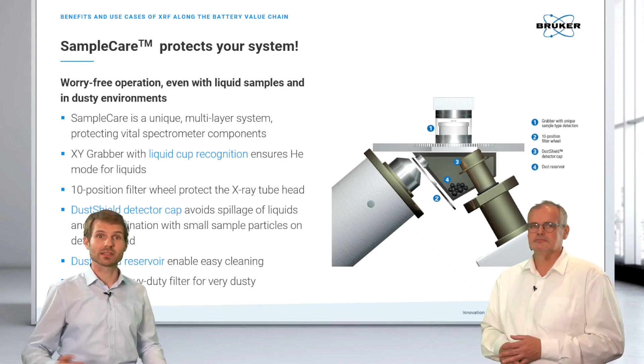On the detector side, we have a detector with an entrance window. It's a semiconductor detector. We can imagine it's very complex technical equipment, and we need to protect it. The S2 Puma comes with a dust shield in front of the detector. So when we have spillage of liquids or loose powders, the shield avoids contamination, and in case something happens, it's quickly exchanged. There is a small reservoir, and in this reservoir the particles are collected and can be cleaned by the user themselves. So there is no need for an additional service visit of an engineer. Even in really difficult environments, our systems are ready to perform 24/7. That's basically the take-home message here.